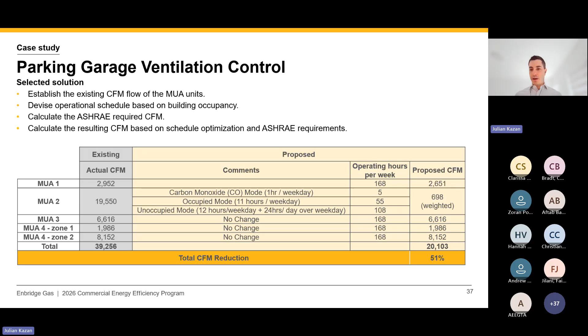How much should it actually be running, right? If we had proper CO detection, if we had proper occupancy setbacks, and what is the actual CFM that should be supplied to that space, right? Based on ASHRAE fundamentals, looking at square footage, looking at zone type, et cetera, right? So, we do that data collection, and then we look at the proposed case about how it should be operating. And then we have a delta between the hours of operation. We have a delta between the CFM, and then we can come up with a saving value, right? You're saving over 20,000 CFM of heated fresh air that you don't need to supply anymore.